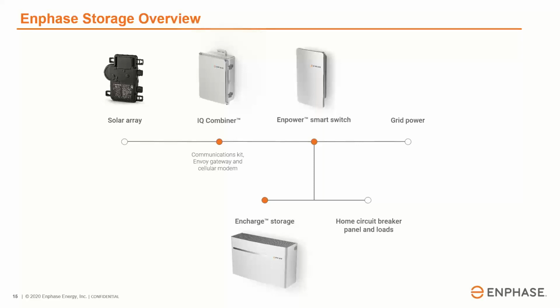You can do customers on a CSS tariff, for example, but the tricky part is you'd have to suspend the PEL limit on the battery to allow it to discharge during the 2-hour period HECO calls for, then reapply the PEL limit. From a technical perspective it's actually a pretty heavy lift, and that's why a lot of folks without a retrofit product are a bit hesitant to participate, because it's a pain in the neck and the value prop isn't as good. So we don't currently enable that CSS application.